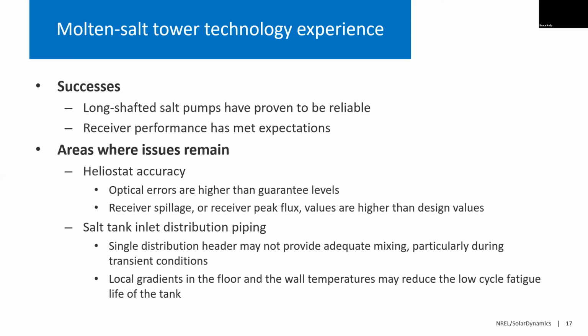The temperature gradients lead to stress gradients, and it doesn't take much of a temperature gradient, something on the order of 20 to 30 degrees C, to establish stresses that are comparable to what you'd see in Section 2 of the code. There have been standard approaches to ring header design, but it's not really known if these are adequate. Are you generating, particularly under transient conditions, stress profiles in the tank that can compromise the low cycle fatigue life of the tank? It's not really known, but some additional work is required along these lines to come to a better understanding of the flow distribution in the tanks and how best to control it, perhaps with different ring header designs. I'm not really sure, but it's a topic that's worthy of additional research.